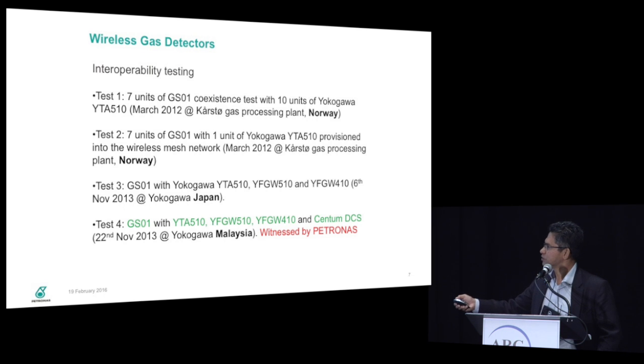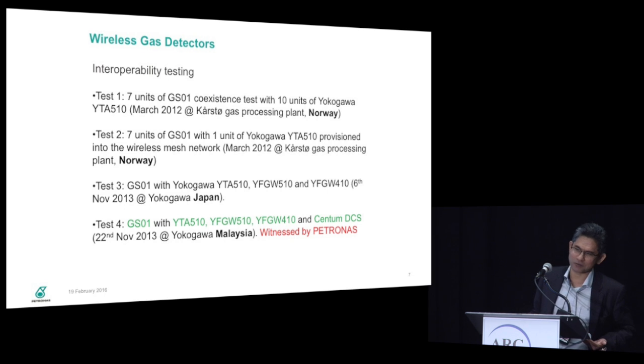The product maturity is compliant to the ISA 100.11a wireless communication standard, satisfying the EX requirement because we are going to install in the explosion-proof areas. Interoperability with the existing wireless network and host DCS. In this case, our host DCS is Yokogawa, used for monitoring purposes only. Wireless gas detectors cannot be used for safeguarding. They can only be used for monitoring.